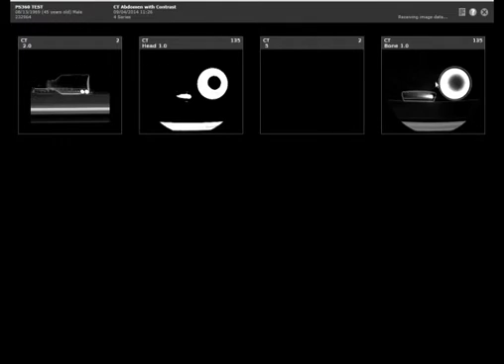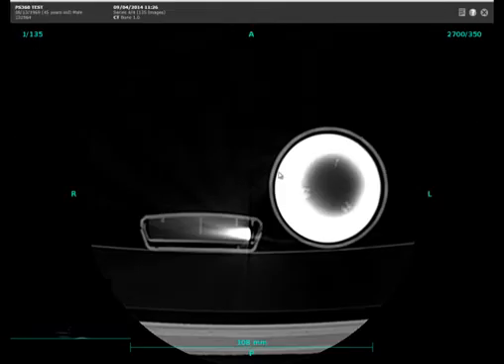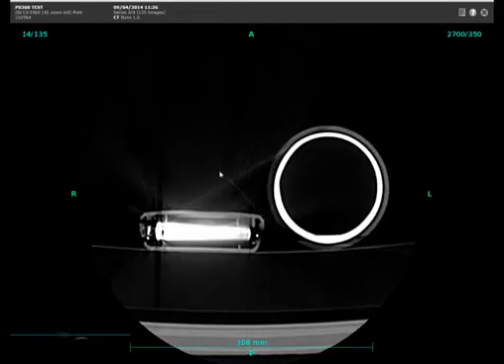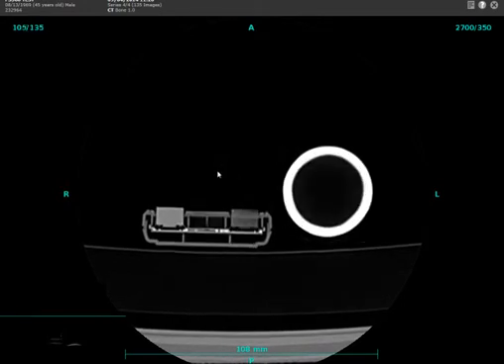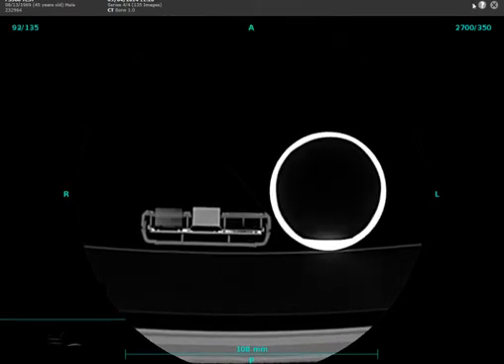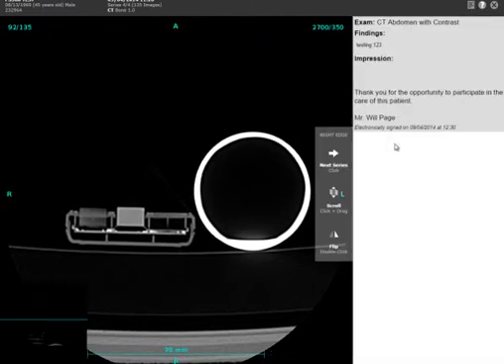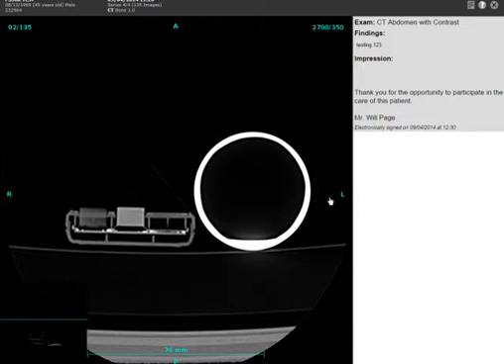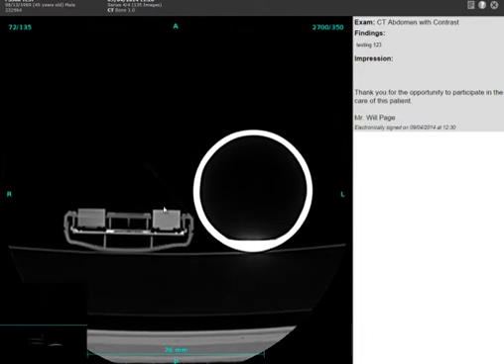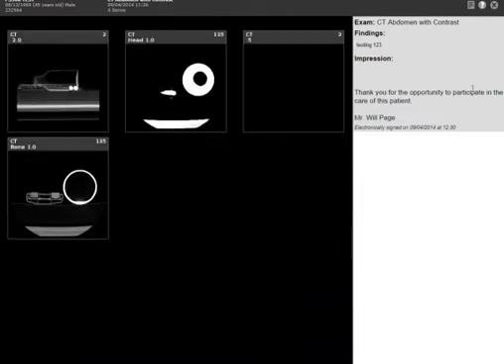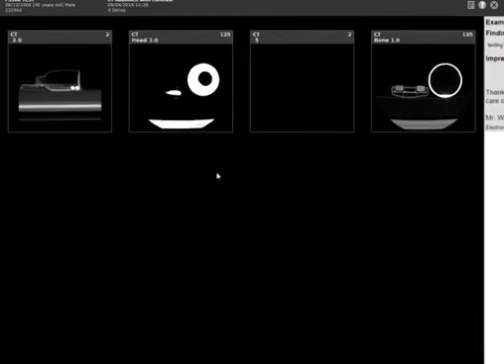Now I can see all the different series. I'll go ahead and open one — I can scroll through the images using my mouse wheel. If I want, I can come up to the report icon, click that, and it brings a copy of the report out to the side. Of course with test data there's not much to see, but you would have a full report come out down the side that you could reference alongside the images. That report stays there until I click the button again, even if I go back to the thumbnail view.